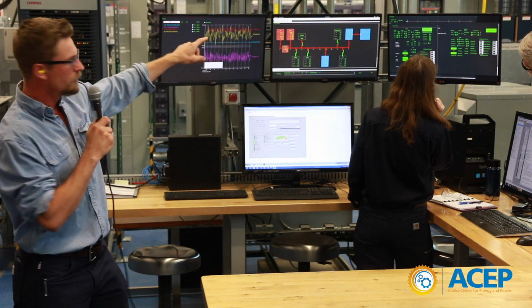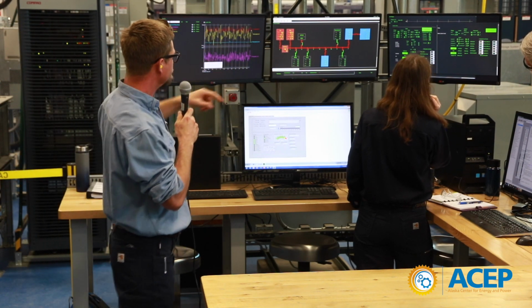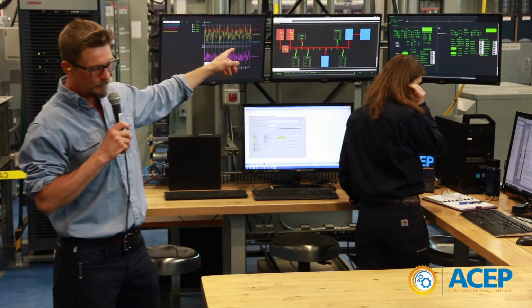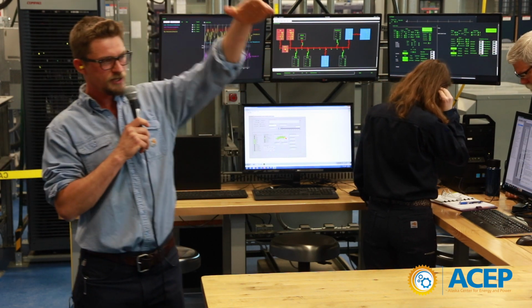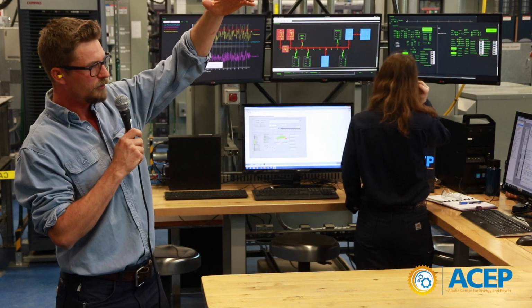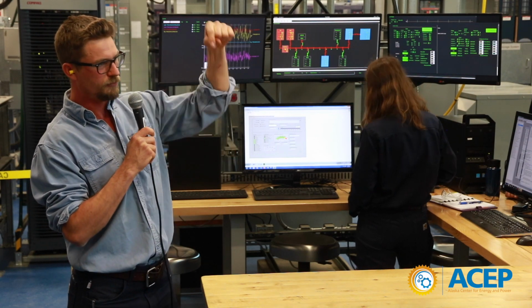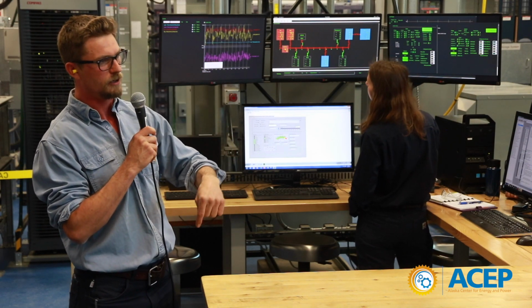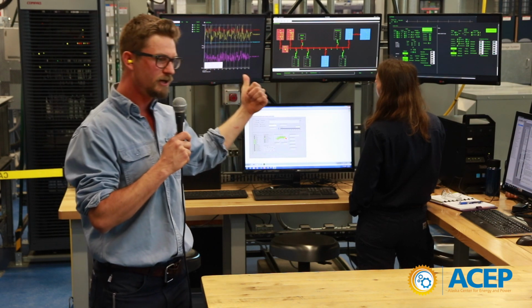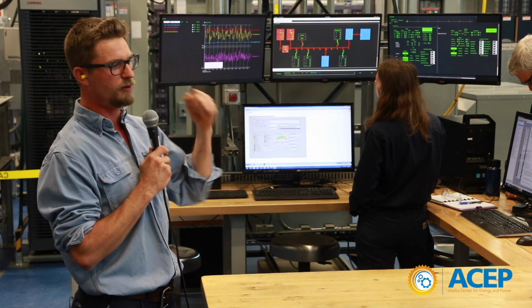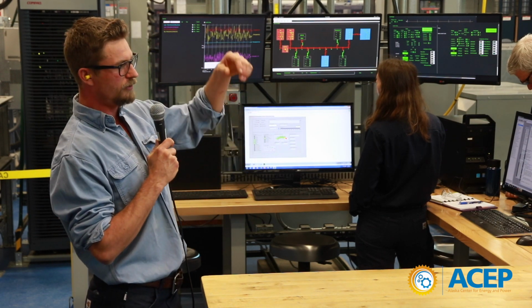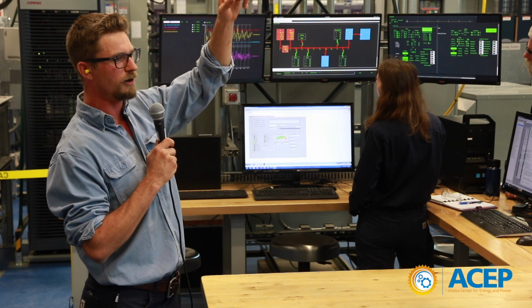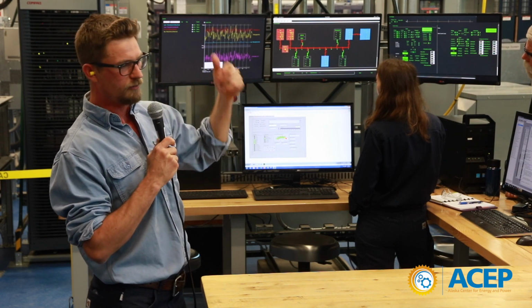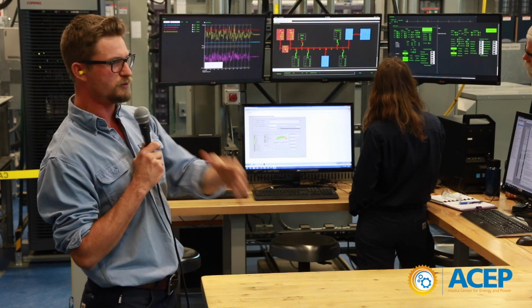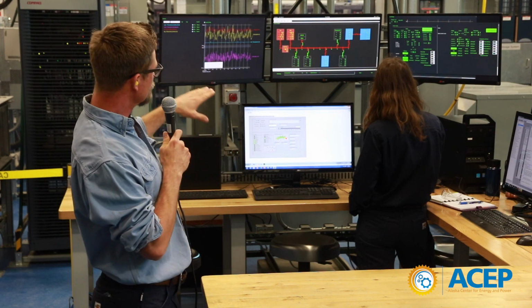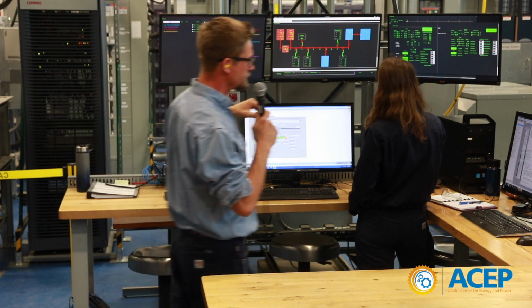Remember when we looked at our frequency plot, when there's a step up in the load, the frequency goes down. That means there's not enough power, so our battery helps out the generator by putting power into the grid. When frequency goes up, that means there's too much power, so our battery or inverter helps out the generator by absorbing power. But for normal operation, it just sits at zero.